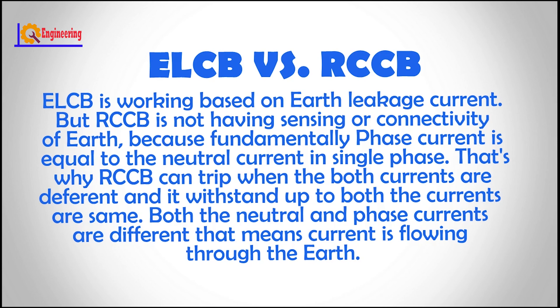ELCB works based on earth leakage current. RCCB does not have sensing or connectivity of earth, because fundamentally phase current is equal to neutral current in single phase. That's why RCCB can trip when both currents are different, and it withstands as long as both currents are the same. If both the neutral and phase currents are different, that means current is flowing through the earth.